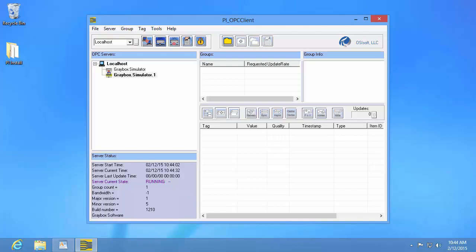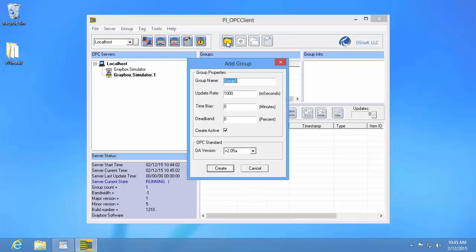Now that we've connected to our OPC server, we're going to want to browse for data. Before we do that, we actually need to create a group. A group is something that exists within the OPC DA standard — it's essentially how OPC clients organize the data they're requesting from the OPC server. On the PI system, we organize data by tags; for OPC DA, these are organized by items, and an OPC client needs to organize these items under groups. To create our group, we press the 'Add a Group' button. This brings up the add group dialogue. Since we're primarily using the PI OPC client tool to validate data, the options don't matter too much, so I'll just hit Create.